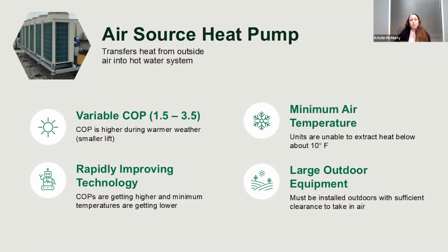There's a minimum to how little heat they can handle. Right now they can go down to about 10 degrees, 0 degrees Fahrenheit, but that number is changing all the time—it's getting better and better, and COPs are getting better too. It is very large outdoor equipment and needs sufficient clearance; you can't just have it hugged up against a building because it needs room for the air intake. And it's noisy, so sometimes people don't want to see it, since we often talk about minimizing the appearance of equipment on campus. This does not minimize it.